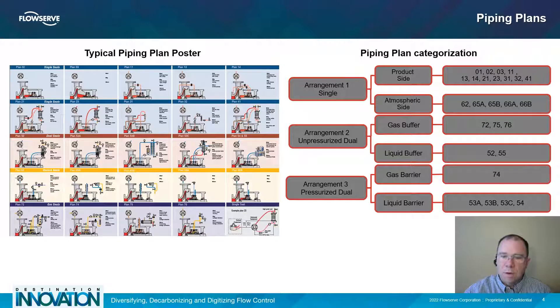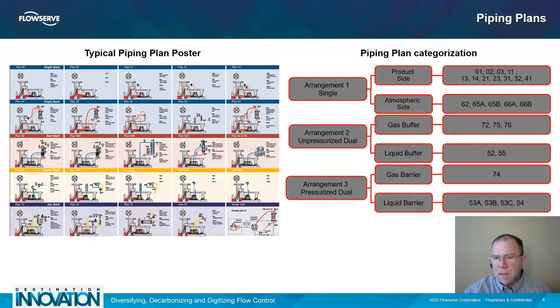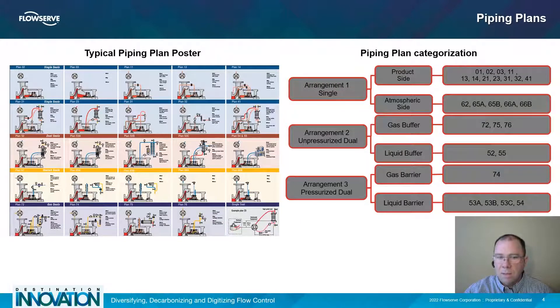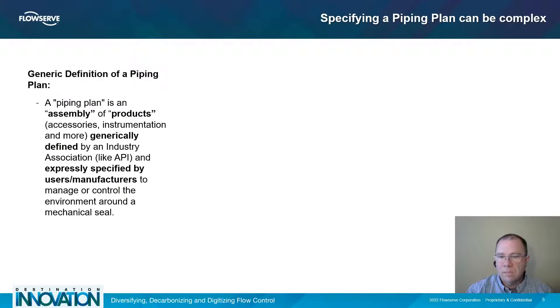As you start to select a piping plan, it's very important to first narrow down your choices. There are a lot of different piping plans available, as demonstrated by a typical piping plan poster available from any mechanical seal manufacturer. First, focus on the type of mechanical seal you have — whether it's a single seal, unpressurized dual seal, or pressurized dual seal — then focus on what you need that piping plan to do. This process will narrow down your choices and make it much easier to select the proper piping plan for your application.